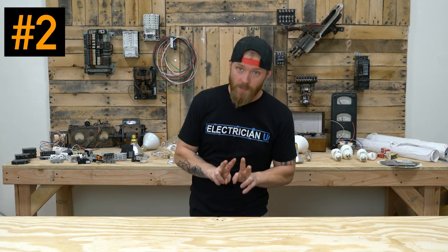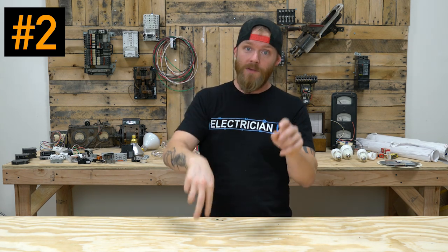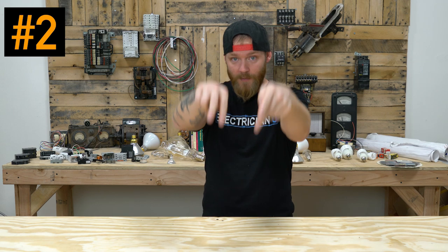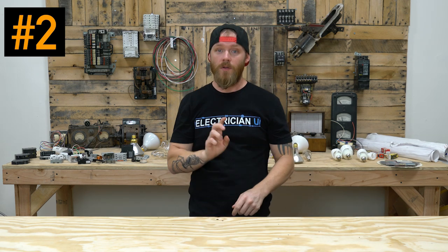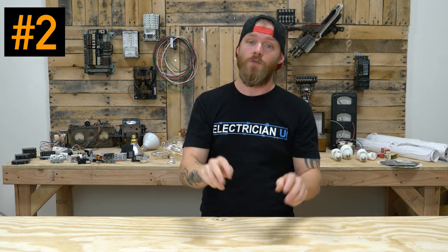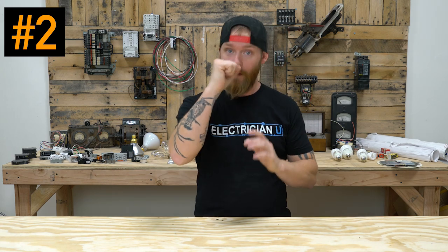The benefit of something like this is that instead of having to run two pieces of 12-2, so you have a hot and neutral running two different runs to the same piece of equipment, you can run one run that has two hots and a neutral inside of it, all in one drop.